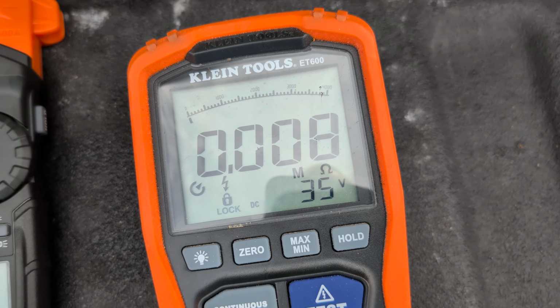So why do you need a megohm meter, a Megger like this ET600? What's the use of it? Well, a lot of times when you have a ground fault circuit breaker or ground fault receptacle tripping, you're not going to be able to detect that ground fault with a regular ohm meter. I've got this in continuity mode. If I'm shorting it out, probe to probe, it can detect that.